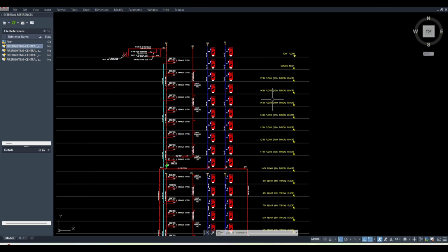Okay, the dry type we use in places where freezing problems are there, mostly in Europe and the USA, where the temperature falls below 0 degrees and the water inside the pipe starts freezing. In that case, the complete system goes out of order and is not operational anymore. So in those cases, we keep the pipe hollow, filled with nitrogen gas, and the sprinklers are there without ready water, and there is a valve outside of that one. From there you can operate it. Once the fire happens, only then does it allow water to go, and the water which is kept to be thrown is above 1 degree temperature, so they make sure it doesn't get frozen because of that environment.